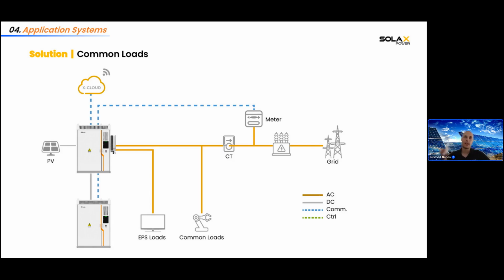And in this case, normally the battery gives power to the loads when we have the grid connected, and also to the EPS loads. And when we have a power outage and the grid disconnects, we can still supply the EPS loads uninterruptedly with 10 millisecond switching time until the battery is discharged or we don't have any PV left. So that's the first and easiest installation solution.